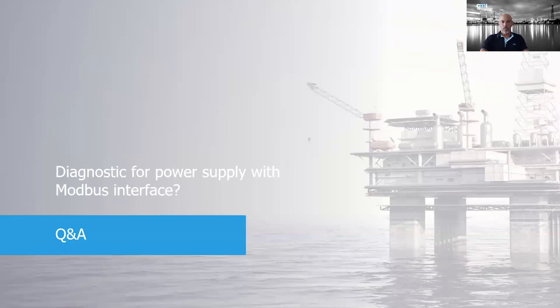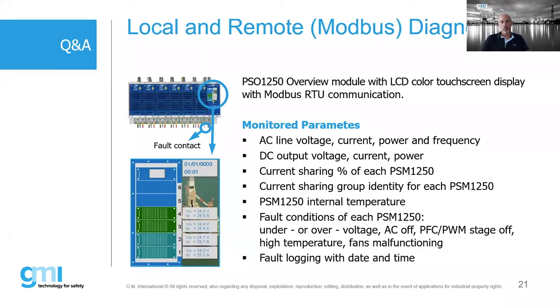Another question we got from you was diagnostics for the power supply with the Modbus interface. Yes, of course, there is a possibility. In our system, we have a solution, we have a panel unit that is optional, that you can install, to read the parameters of the power supplies for all the connected modules. In this example there are six modules connected, and all six modules are monitored by the unit over there, which can alert the system through multiple contacts, two contacts, and also through Modbus. Through Modbus, as a Modbus slave, you can connect to your Modbus master, the DCS or the safety PLCs or the PLCs, and read all parameters regarding the modules. Locally you can also see all parameters, but that is limited to the number of modules you have there. That is one option.